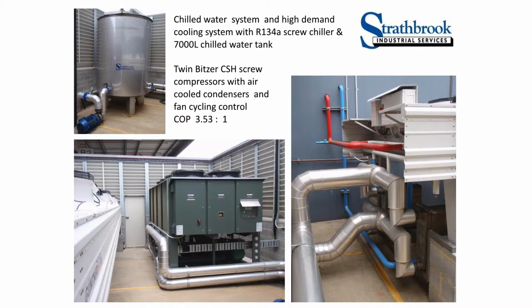At the bottom you can see a twin screw compressor R134A screw chiller. Probably not the most energy efficient way of doing this, but it was what the budget that Meyer's gave us would allow for. So there's a 7,000 litre chill water tank. The chiller pumps the water out of the tank through the plate heat exchangers and back into the tank, and it might only run the compressors for 5 minutes an hour on a 30-degree day, because it's sized to work on a 45-degree day, and every time I drop the condensing temperature by 1 degree, I take 4% of the load off the chiller.